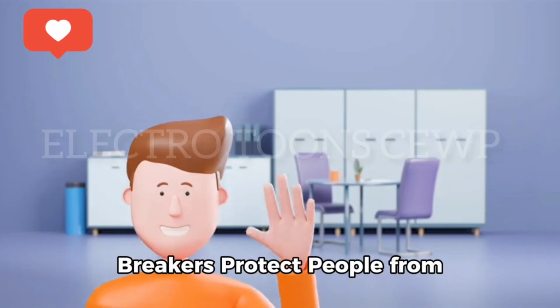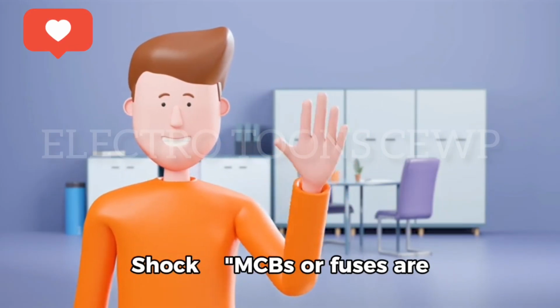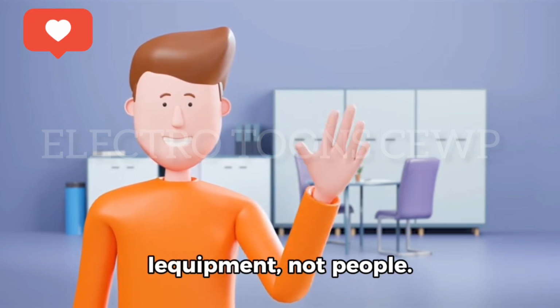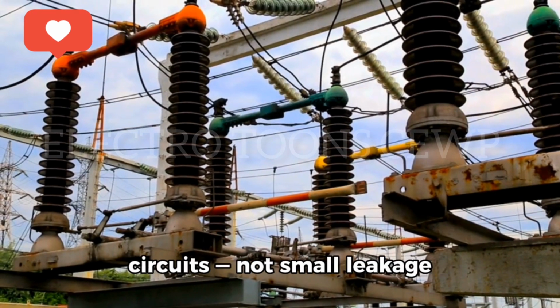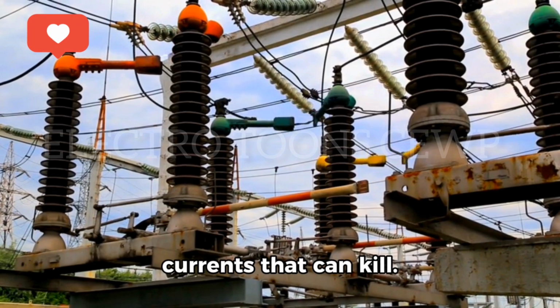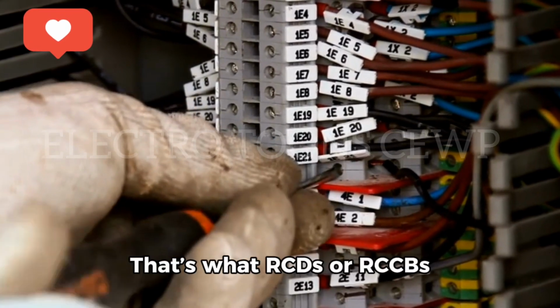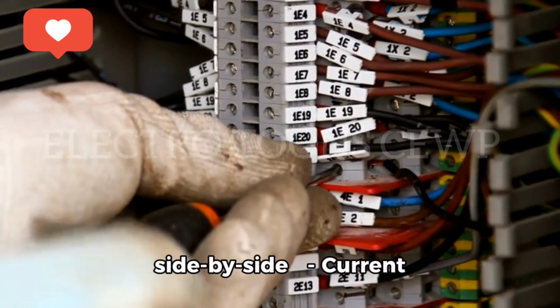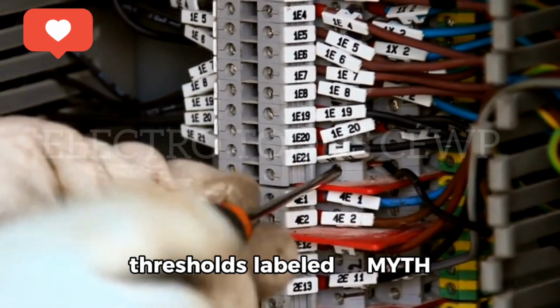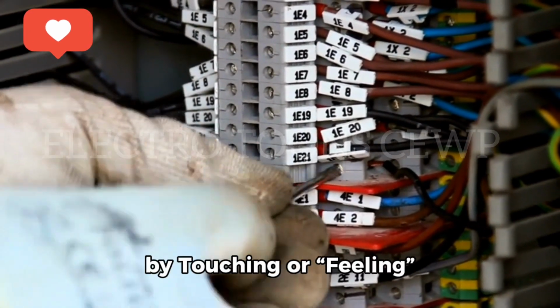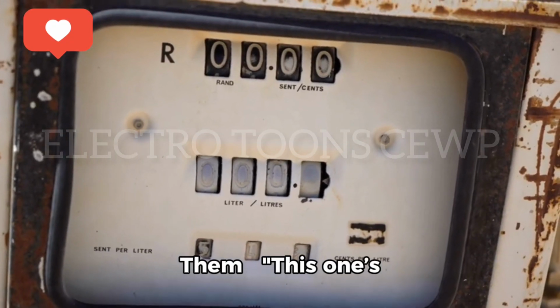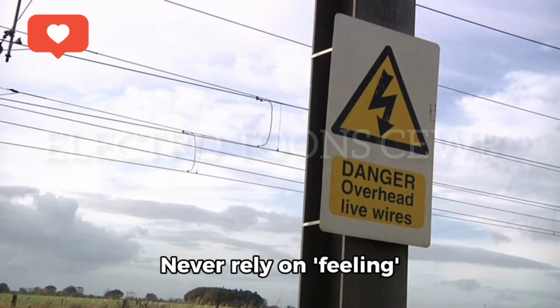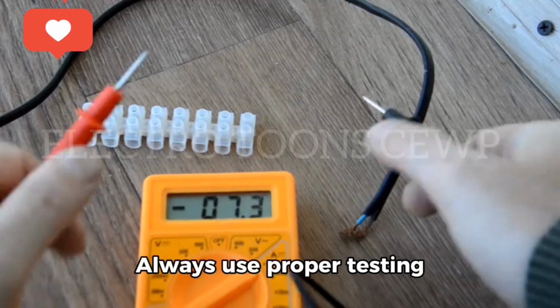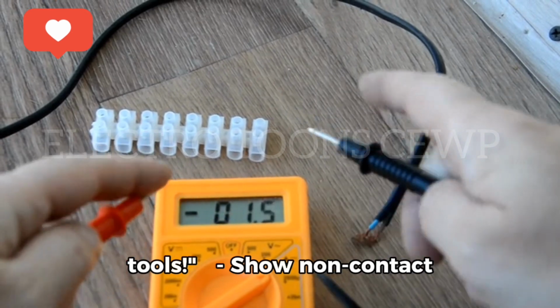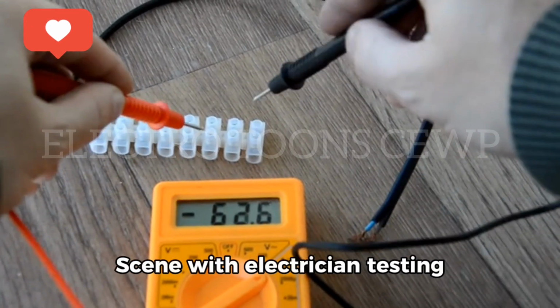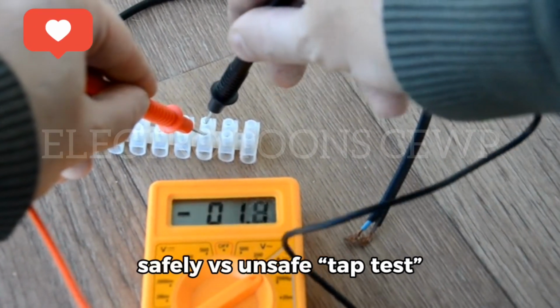Myth 8: circuit breakers protect people from shock. MCBs or fuses are designed to protect equipment, not people. They trip on overload or short circuits, not small leakage currents that can kill. That's what RCDs or RCCBs are for. MCB versus RCCB side by side. Current thresholds labeled. Myth 9: you can test wires just by touching or feeling them. This one's extremely dangerous. Never rely on feeling if a wire is live. Always use proper testing tools. Show non-contact voltage tester and multimeter. Scene with electrician testing safely versus unsafe tap test.